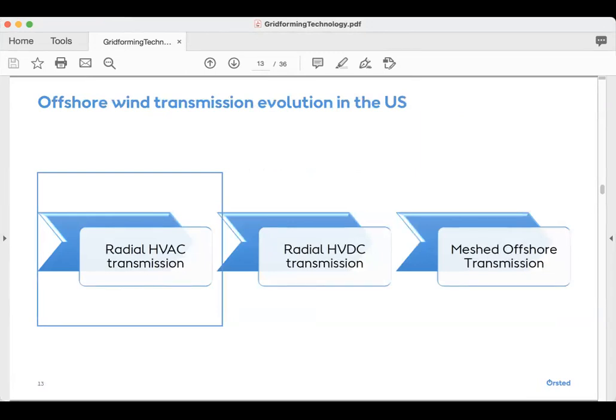If we look at how offshore wind transmission evolved in the US, we first started off with radial high voltage AC transmission. What do I mean by that? There's one wind farm, about 800 megawatts to 1100 or 1200 megawatts, connected radially to a point of interconnection - it could be one or many points of interconnection - through a high voltage AC export cable. So there's no shared transmission in this concept. This was the initial phase of offshore wind development on the East Coast, because we could find points of interconnection very easily for the first few projects.